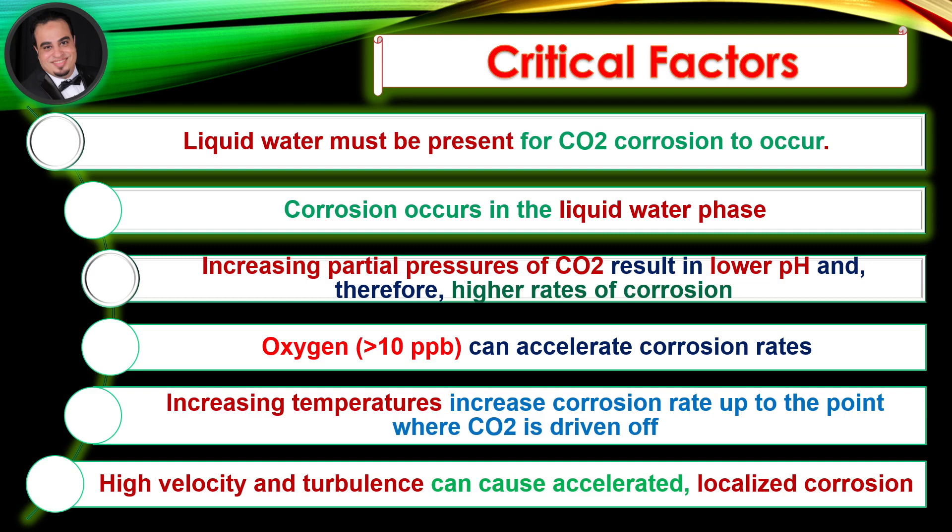Oxygen at more than 10 parts per billion can accelerate corrosion rates. Increasing temperatures increase the corrosion rate up to the point where CO2 is driven off. High velocity and turbulence can cause accelerated localized corrosion.